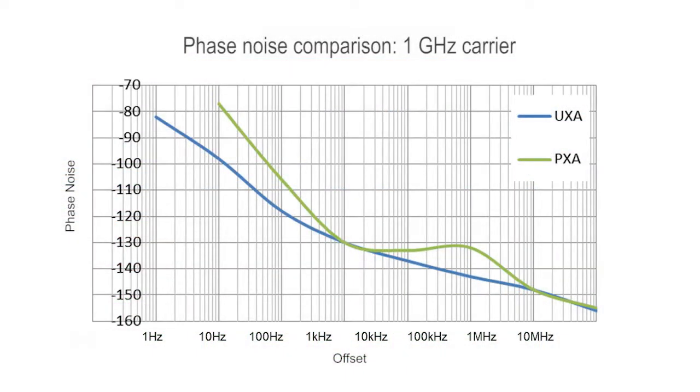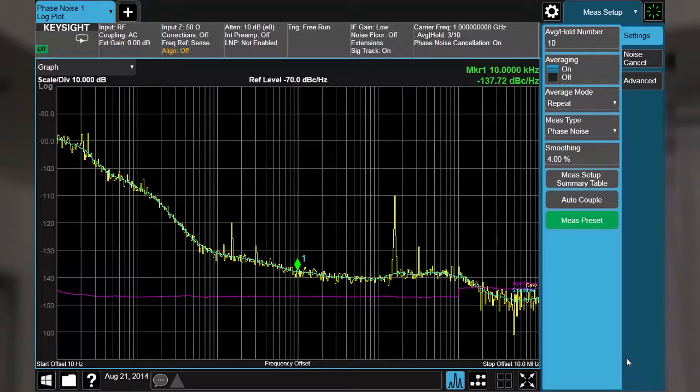The UXA has significantly improved the phase noise compared to our PXA signal analyzer. This is important if you are measuring an oscillator design or testing the latest OFDM standard. The use of a direct digital synthesis LO section, based on a Keysight proprietary DAC, improves phase noise while maintaining excellent spurious performance.